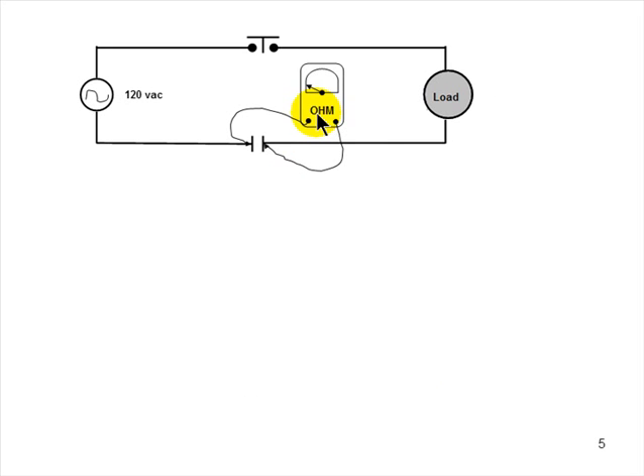Now, this case, we got an ohm meter. Open switch. This circuit then, because this switch is open, is isolated. What should I read here across this open switch? I should read infinity. It shouldn't move. This needle on an analog ohm meter should stay to the left. It shouldn't move. It should be near infinity. If it's a digital meter, it'll say OL, overload, out of range, whatever.